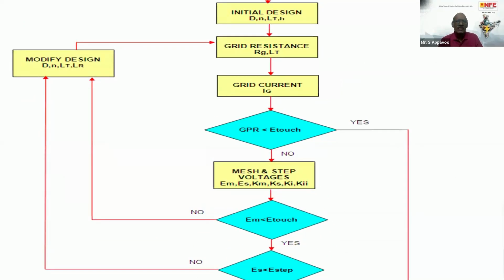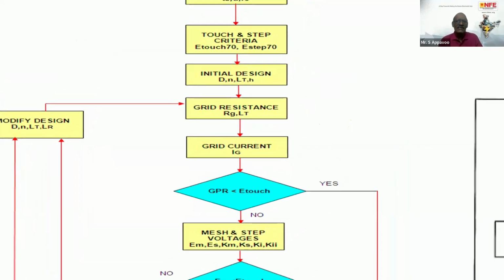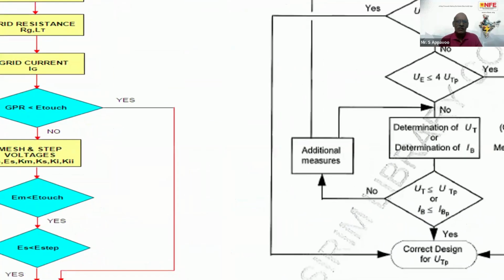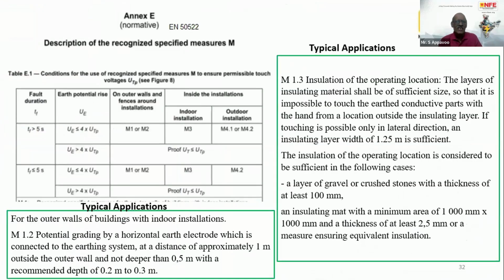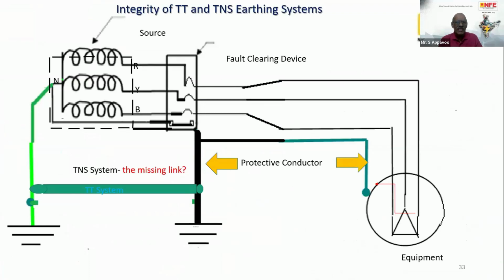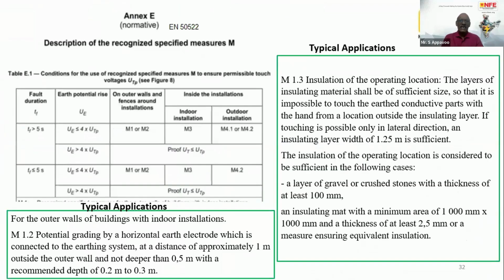What should we do? What is the grid current? What is the grid resistance? What is the initial design? That you can do, no problem. But don't burden heavily without considering the additional measures, because there are already measures available naturally. Thanks to the underground mass of pipelines, of utility, railways, everything, there is always a parallel path. Not all the ground current passes through our substation. Most of it is diverted through the overhead conductors, cranes, as well as the earthing conductors, as well as the invisible earthing conductors of utilities.